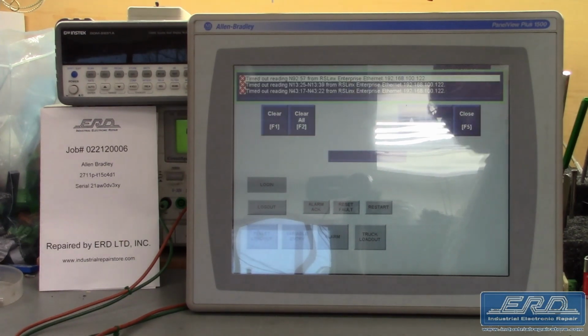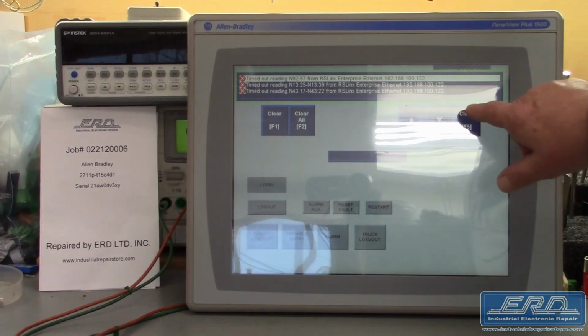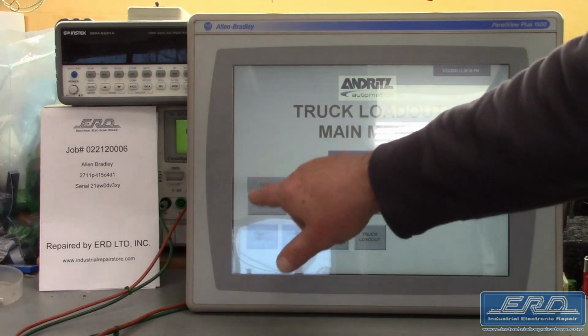We rebuilt the power supplies and repaired the video section. We backed up the program in the display, but we did leave it intact instead of resetting the memory to default, so this unit was ready for immediate use in their customized control system.